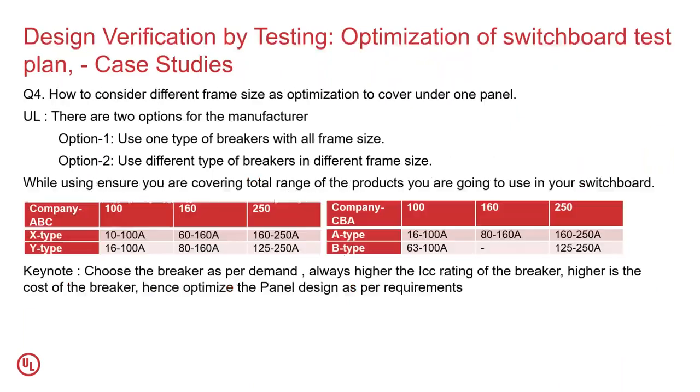Let me see the example. There are two options you can use. Option one is to use only one type of breaker. Option two is to use different types of breakers with different frame sizes. Refer to the example: company ABC has X type with 10 to 100 amps, 100 amp frame, 160 amp frame, 250 amp frame. And Y type, again 16 to 100 amps, 80 to 160 amps, 250 frame, 125 to 250 amps.